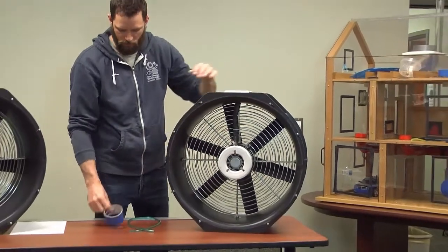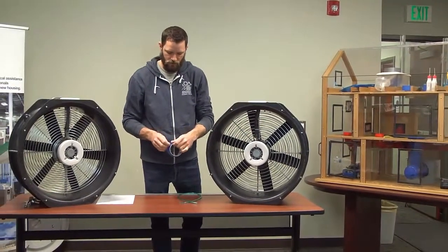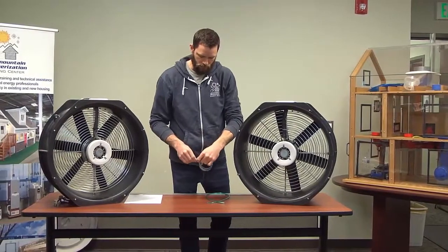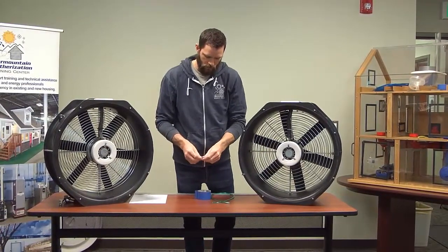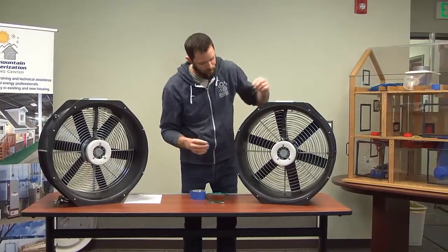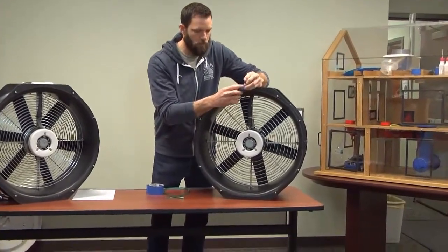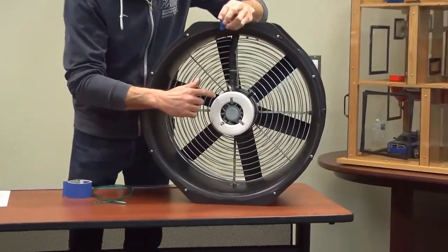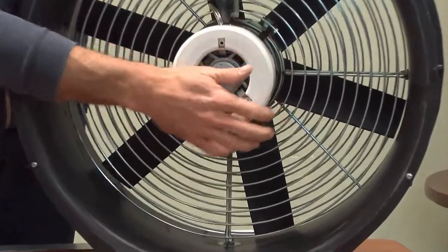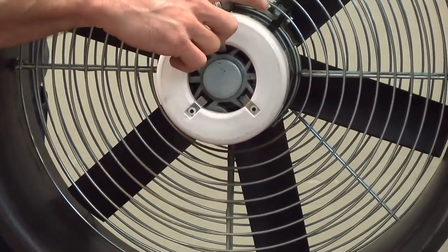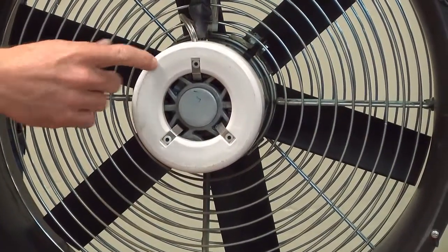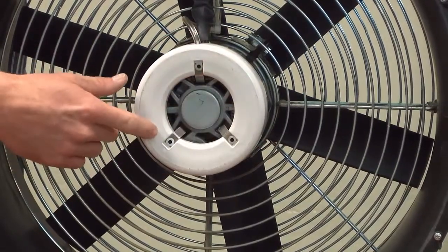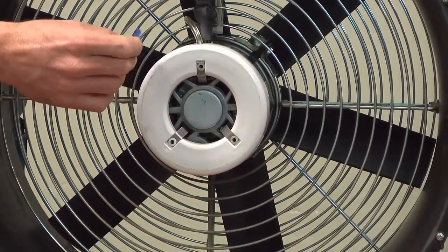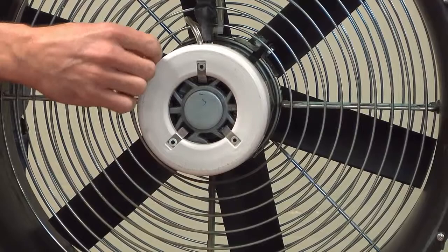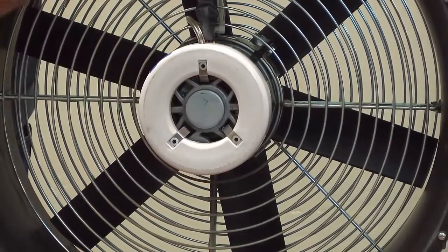And how we check for the leakage is we're going to take just some masking tape. There are four sensing holes on the flow sensor, positioned at 10 o'clock, 2 o'clock, 4 o'clock, and 6 o'clock on the housing, and we're going to cover those sensing holes.